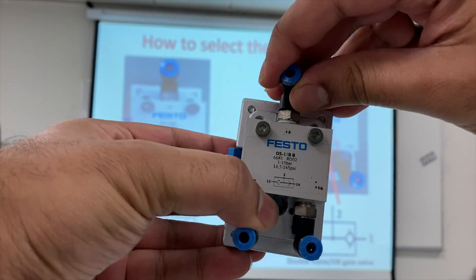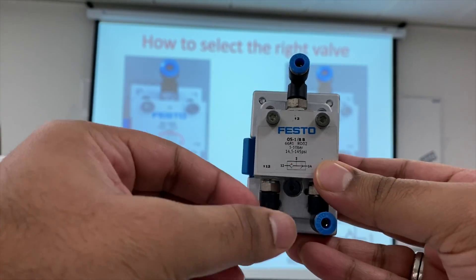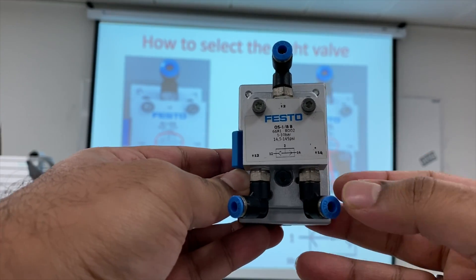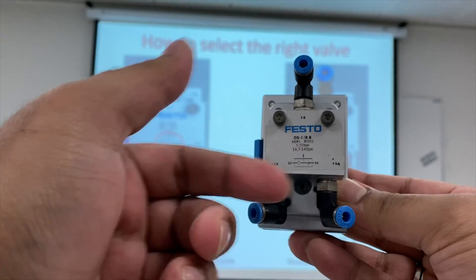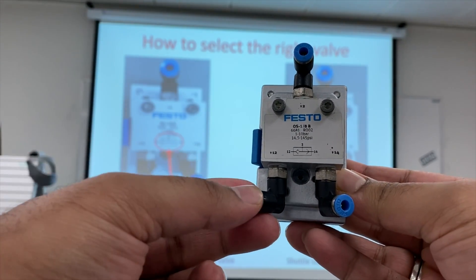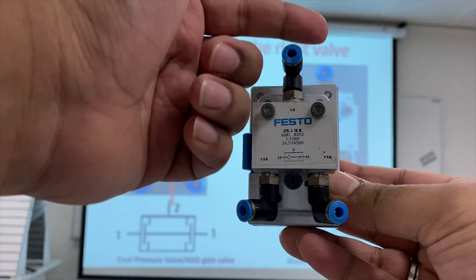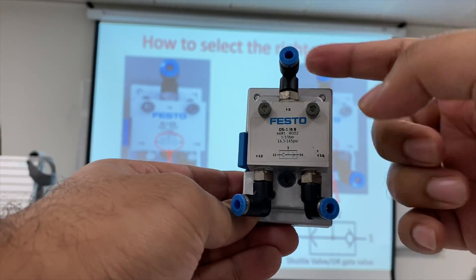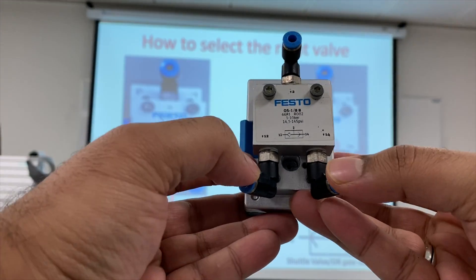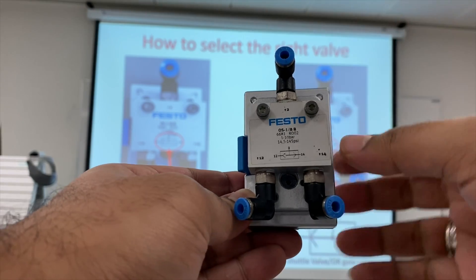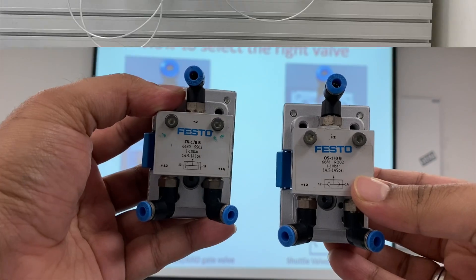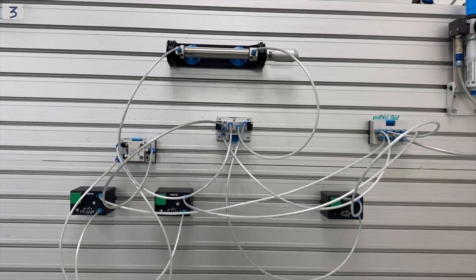For the shuttle valve, we again have the left side and right side feeding into port two. If air comes in from the left side, port two will be activated. If it comes in from the right side, port two will be activated. If it comes in from both directions, port two will also be activated. That's the difference between the AND gate and the OR gate.